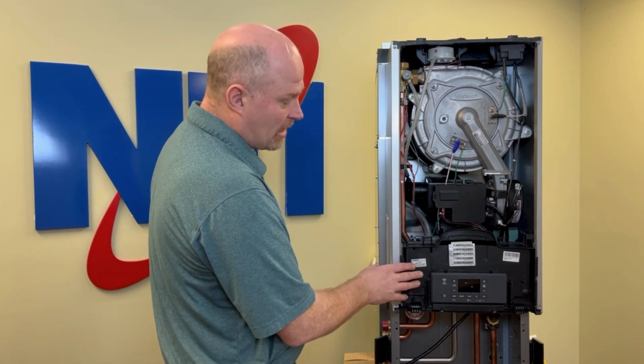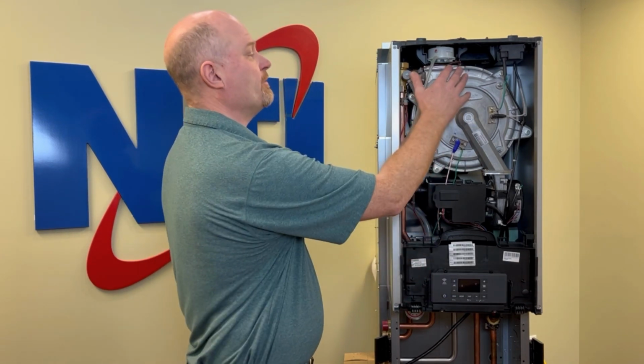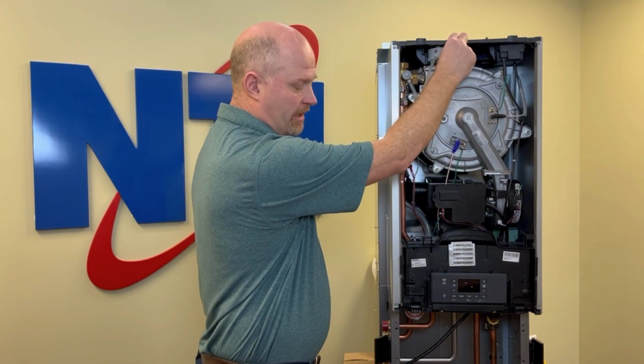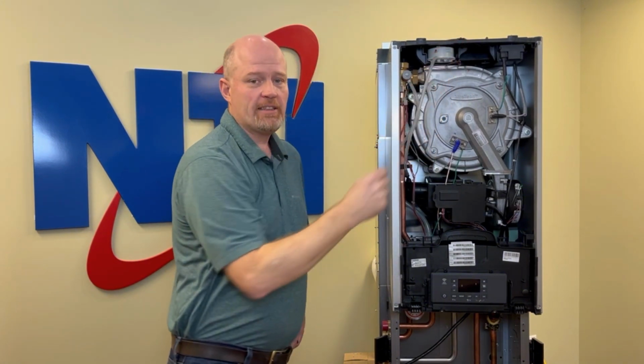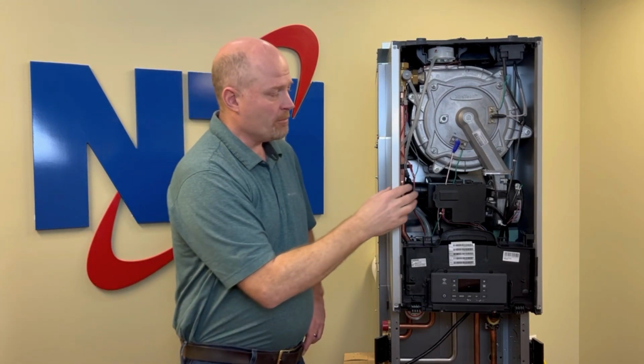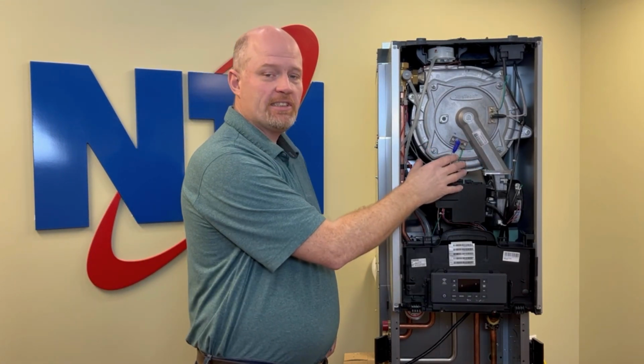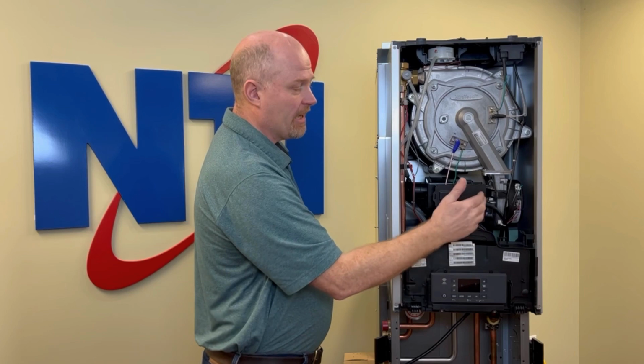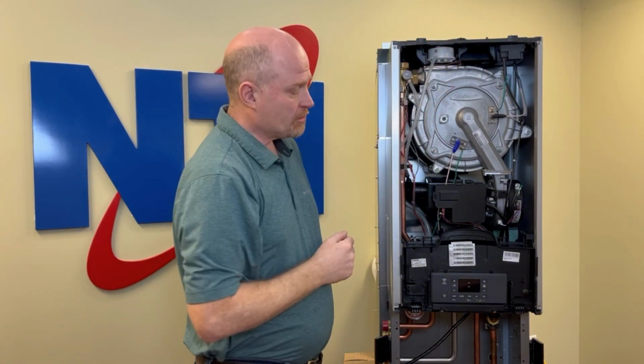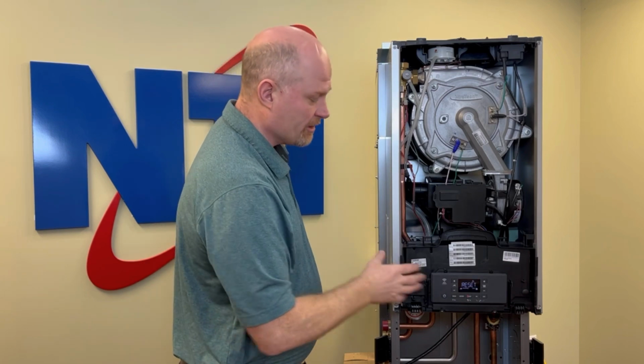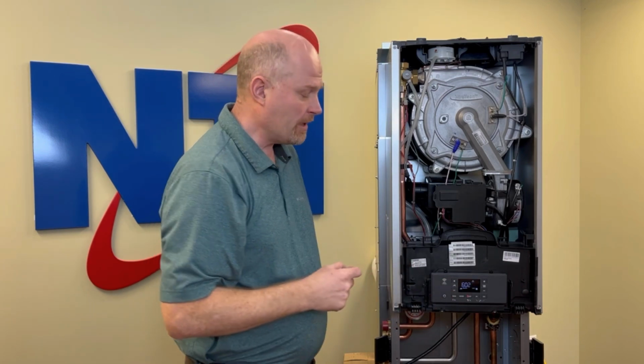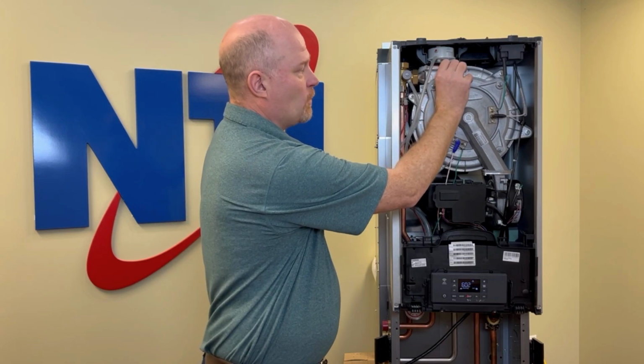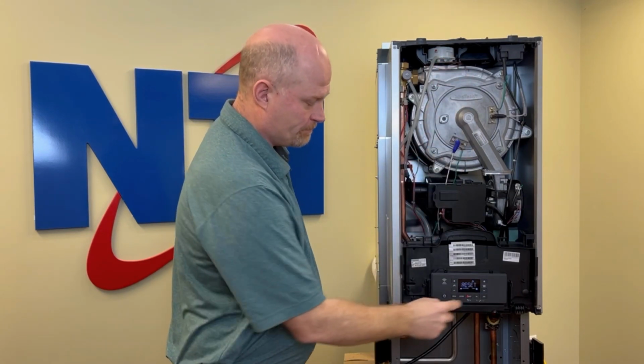It's very important anytime you get a 602 that you double check the flue gas temperature of the boiler using your flue gas analyzer in the test port. Measure the flue gas temperatures. A general rule of thumb is that your flue gas temperature should never exceed the return water plus about 20 Fahrenheit. So if your return is coming in at 160, we would never expect to see a flue gas temperature above 180. If the flue gas measures cold or cool with your flue gas analyzer, but the boiler is reporting a much higher temperature, that indicates the sensor is damaged or these wires have become wet or corroded in some way.